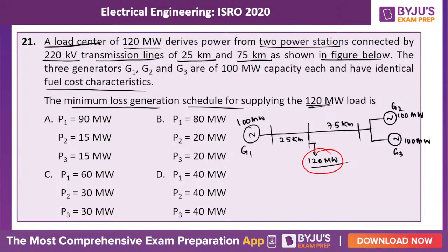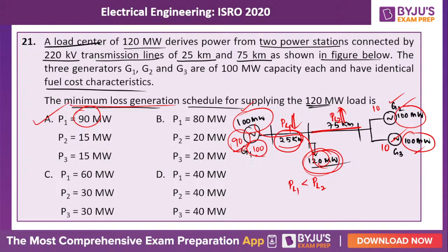So the best possible answer is A. If you place 90 megawatts on generator 1, with generator 1 sharing 90 megawatts load, the remaining 30 megawatts has to be shared by generator 2 and generator 3, 15 each. Why is it shared equally? Because the distance of the transmission line is 75 kilometers for both generators, and the fuel cost characteristics are also the same. So you cannot simply place 30 megawatts on a single generator because this one is also operating, no? So for economical load division, you have to divide the load properly. So the best option is A.